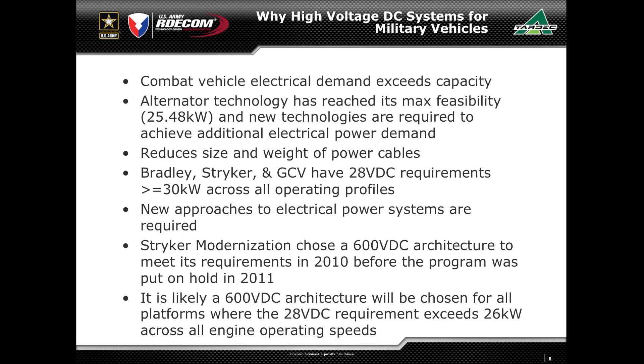Now why 600 volts? I wish there was a nice technical reason for why we chose that number, but I'll walk you through the trades I was involved with and how we arrived at it. When I was on Stryker, we did an ISG trade study which showed we were trying to achieve a certain power density. What we learned is that the current rating on each phase of the ISG needed at least 400 volts AC phase-to-phase to achieve the power rating of 120 kilowatts and the size density we were looking for. So they said we should have at least a 400-volt DC system or greater.